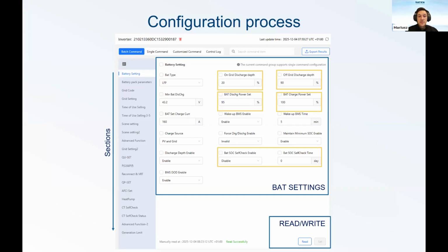The most important are the on-grid discharge depth and the off-grid discharge depth. The on-grid discharge depth tells us what percentage of the battery we want to use during on-grid mode for self-consumption or peak shaving. The off-grid DOD tells us what maximum percentage we want to discharge the battery for the backup solution. So if we have here 20 and 90, that means 20%: we will go from 100% to 80% in the on-grid time. Once we have discharged to 80%, we will not discharge it further. Then we will wait for the power outage, and if the power outage comes, we will discharge it up to 90% of the DoD, down to 10%.